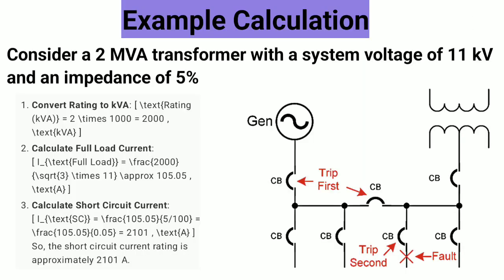Example calculation. Consider a 2 MVA transformer with a system voltage of 11 kV and an impedance of 5%. Convert rating to kVA: rating in kVA equals 2 times 1000 equals 2000 kVA. Calculate full load current: I_full load equals 2000 divided by the square root of 3 times 11, approximately 105.05 A.